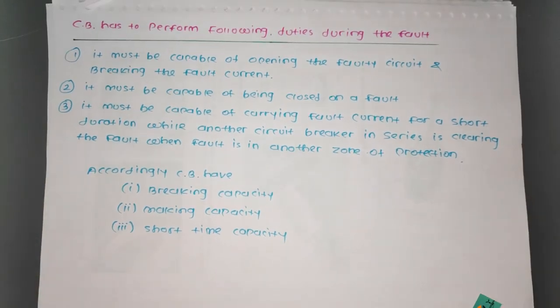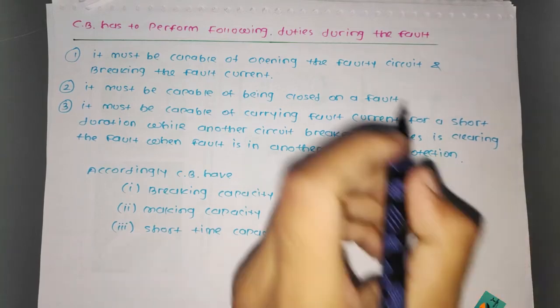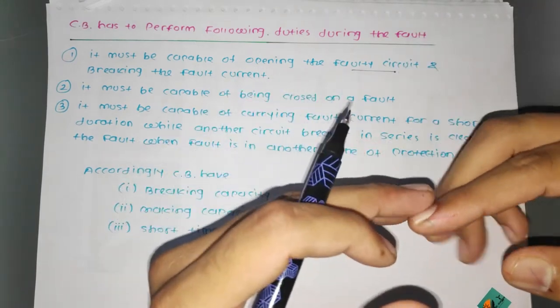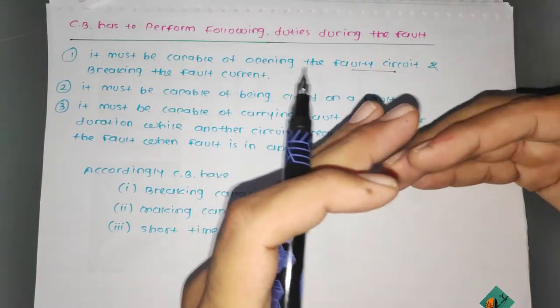The circuit breaker must perform certain duties during a fault. First, it must be capable of opening the faulty circuit and breaking the fault current — so that any fault does not propagate to other parts of the system or affect other healthy phases. Second, it must be capable of being closed on a fault.